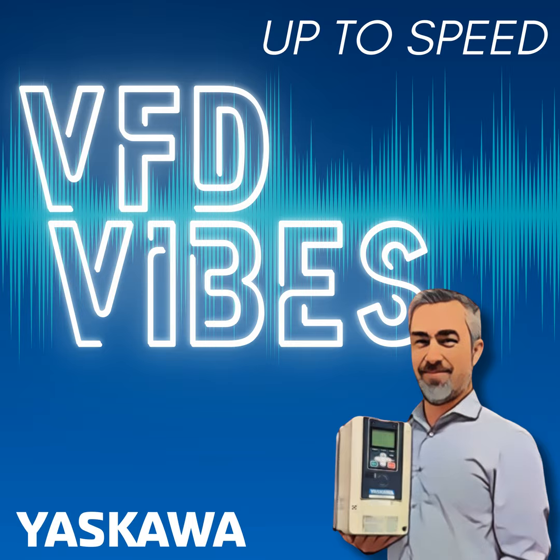So I'd say, okay, very good. Let's make sure we have a run command. There's some monitors. U110 is a monitor that shows our digital input terminal status. And I'd have the service tech find U110 and ask, what do you see in there? It's all zeros. And U110 is a way to check the status. And if all the digital inputs are opened, it will be all zeros.